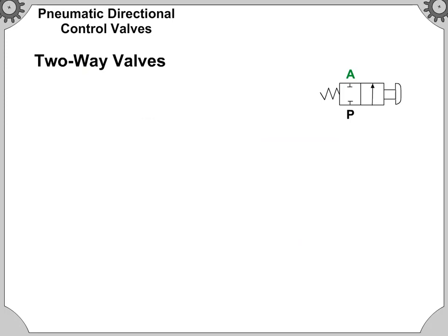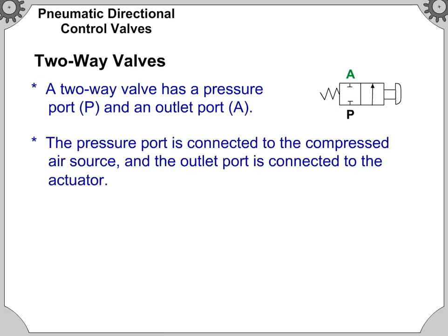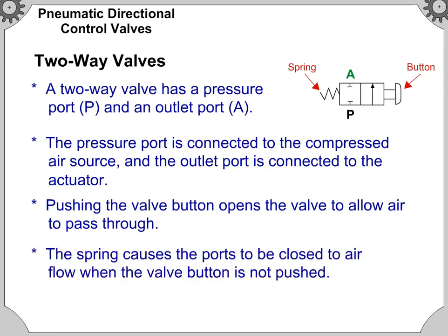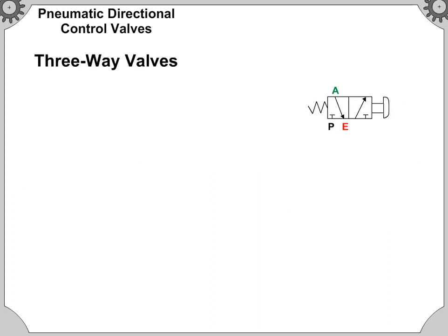A two-way valve has a pressure port P and an outlet port A. The pressure port is connected to the compressed air source and the outlet port is connected to the actuator. Pushing the valve button opens the valve to allow air to pass through. The spring causes the ports to be closed to airflow when the valve button is not pushed. Two-way valves are commonly used to start and stop flow in a particular line.